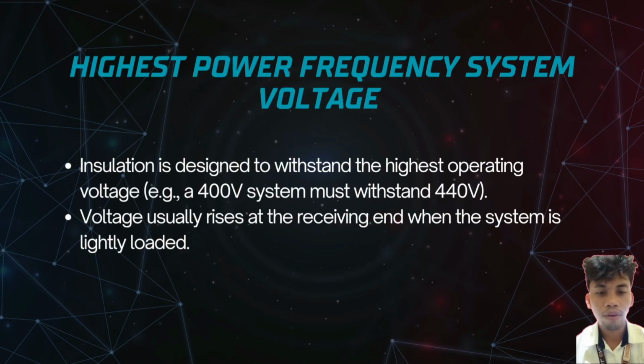And for the Ferranti effect, what is the Ferranti effect? Voltage usually rises at the receiving end when the system is lightly loaded. This is a phenomenon known as the Ferranti effect in long transmission lines or cables when there is very little load, or people are not using much electricity. The line itself acts like a capacitor. This causes the voltage at the receiving end of the line to become higher than the voltage at the source or sending end.